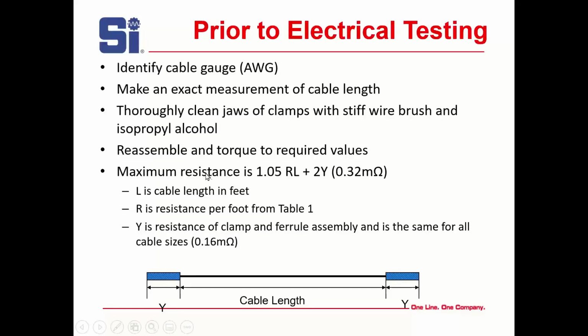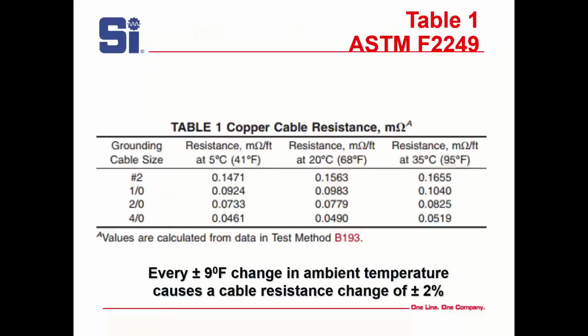And then your maximum resistance should be calculated: 1.05 times (R times L plus 2Y), where R is the resistance per foot, which you can see from the table I'm going to show you, L is the cable length, and Y is the resistance of the clamp and ferrule assembly. It is the same for all cable sizes, at 0.16 milliohms.